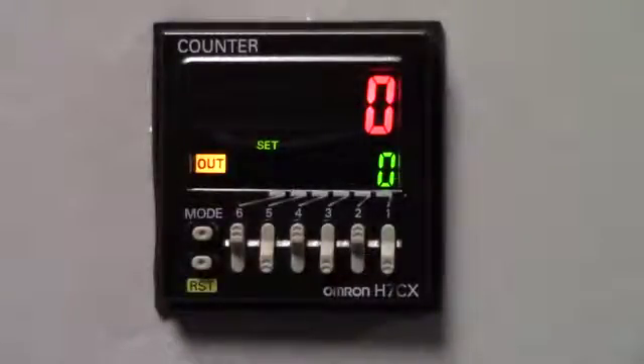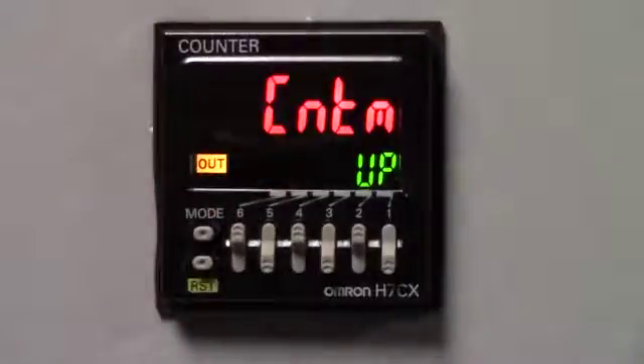What we need to do now is program the function modes. By doing that, we're going to press the mode key and hold it for three seconds. So, now you're going to see CNTM, and that's going to give us the count up function. And for this application, that's what we are going to use. We're going to use the CNTM. This is our input mode. There's five different modes to choose from. So, we're going to keep it at the factory default for right now.